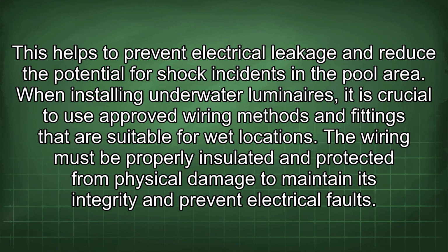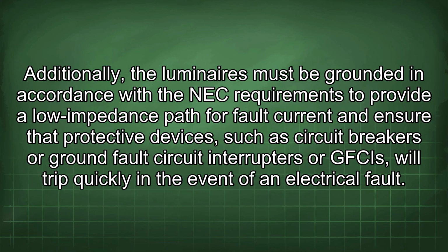When installing underwater luminaires, it is crucial to use approved wiring methods and fittings that are suitable for wet locations. The wiring must be properly insulated and protected from physical damage to maintain its integrity and prevent electrical faults. Additionally, the luminaires must be grounded in accordance with the NEC requirements to provide a low impedance path for fault current and ensure that protective devices such as circuit breakers or ground fault circuit interrupters, or GFCIs, will trip quickly in the event of an electrical fault.